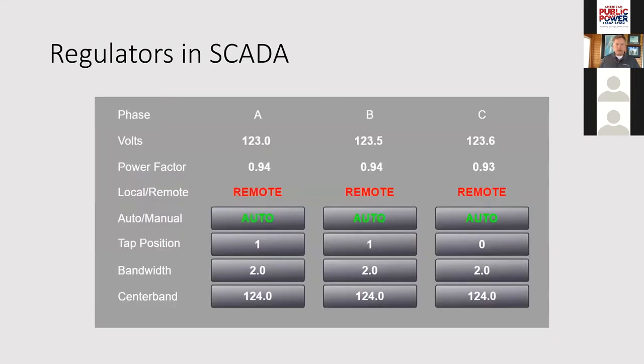This is a screen capture of how we set up our SCADA with the individual regulators. You can see we have set points that we could change. The center band of 124 volts is typical with a bandwidth of 2, so it allows us to range up to 126 or down to 122.